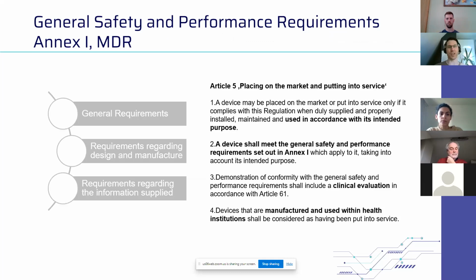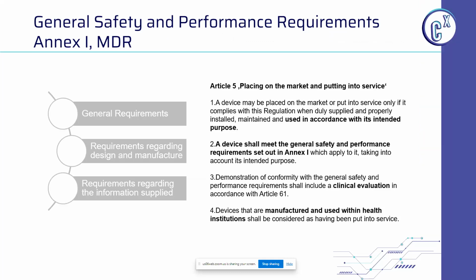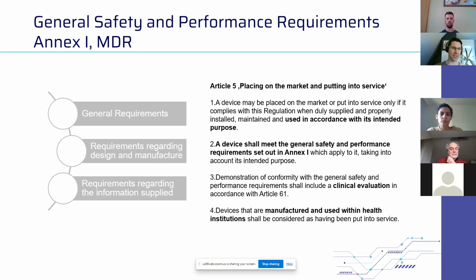Now, I've talked already about general safety and performance requirements. Here, to navigate you into Annex 1 of the Medical Device Regulation, probably the most interesting of the annexes: Annex 1 should be understood as a checklist. Think of every clause as one checkpoint you need to follow, maybe even deconstructed into individual sentences or parts of sentences if you need that. What you can then do is associate with each of those requirements either an applicable standard, or a procedure in your quality management system which refers to or is based on a standard, and then ultimately the technical documentation where you have the evidence that you satisfy the requirements set out in Annex 1.